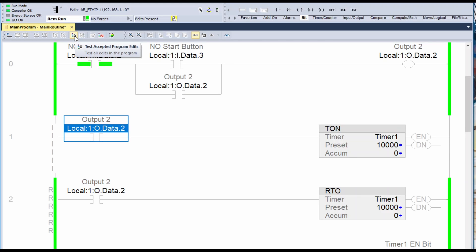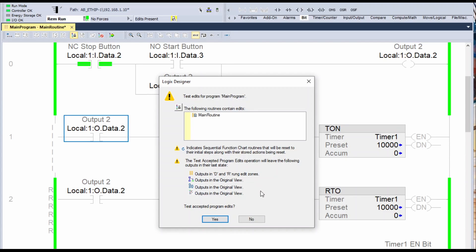The next thing I can do is test the edits by clicking on this. Now keep in mind — from what I've read — when you test these values, the test accepted program edits operation will leave the following outputs in their last state. So keep in mind that until we actually finalize these edits, your outputs may be stuck in their previous state. If you have processes running at the moment, the outputs that were already set will remain set until you actually accept these changes.